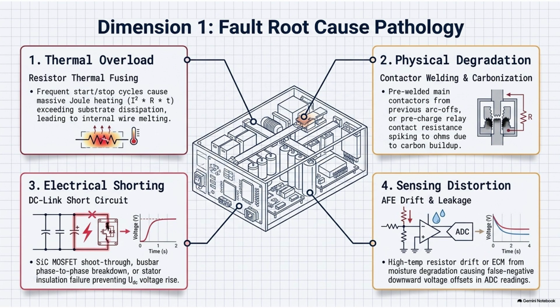Fast forward to the next morning. The driver gets in, completely unaware of this microscopic damage. They press the start button. The car's computer says, okay, initiating safe garden hose pre-charge sequence. But because that main contactor is already physically welded shut from yesterday's plasma arc, the garden hose is completely bypassed, because the fire hose is already wide open.